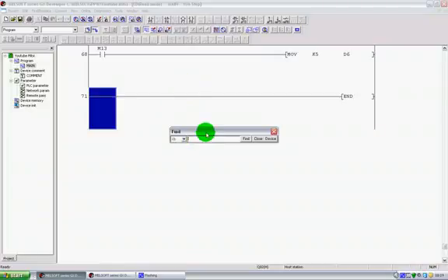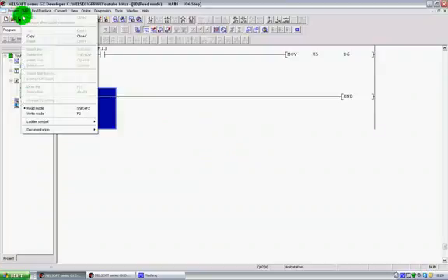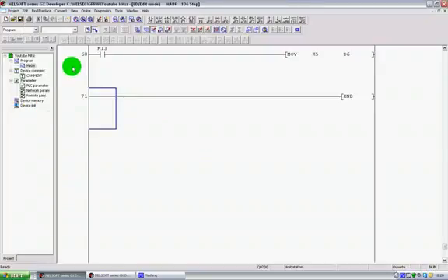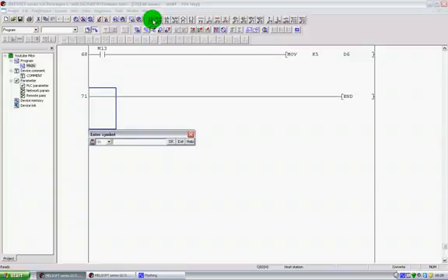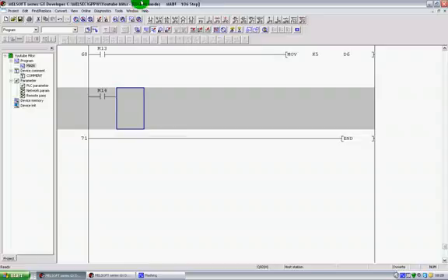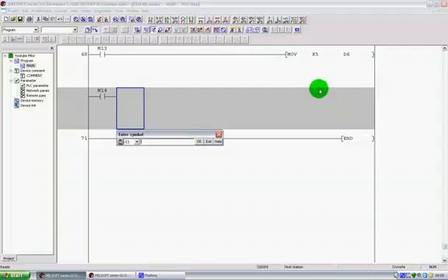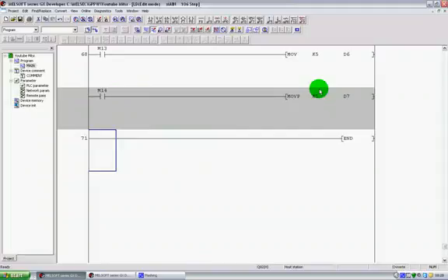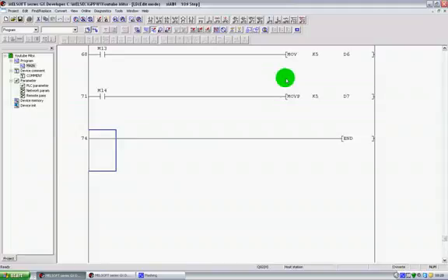You can simply do that by, let's put M14 in. Oops, I've done it again. I forgot that when we go into the simulation we go into read mode, so I've just had to switch it back to write mode. So we go back, put our M14, and now we can move P, and we'll do K5 into D7. Now I'm not going to run this one under the simulation because the only difference here is this P at the end of the move command.